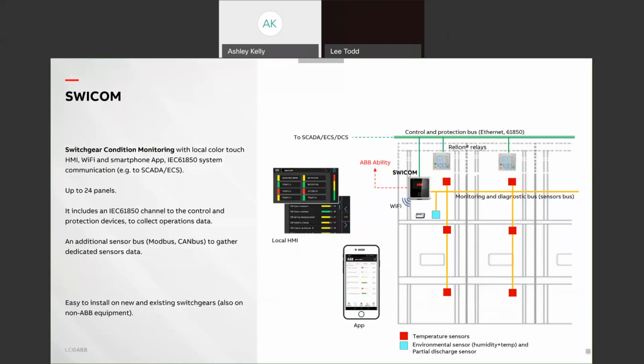Additionally, SWICOM can be read remotely via Android or Apple device, on a local or remote HMI, keeping personnel at a distance from the switchgear. If you imagine pulling this data any other way, you'd finish up standing in front of the switchboard physically making contact with your protection relays.